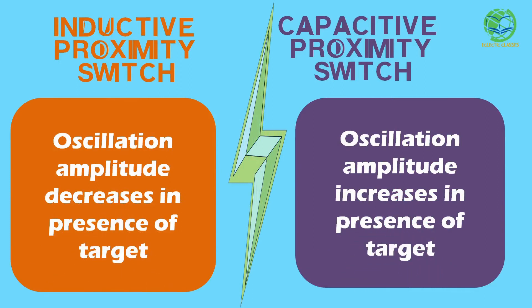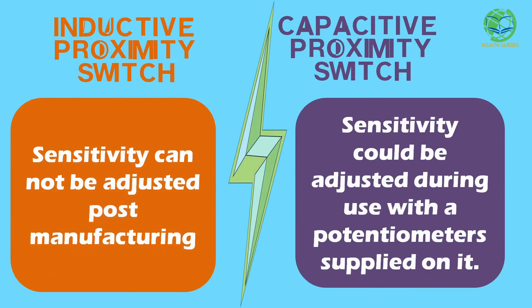In case of inductive sensors, the oscillation amplitude decreases with the presence of the target object, while in case of capacitive sensors, the oscillation amplitude increases with the presence of the target object. Inductive sensors' sensitivity cannot be adjusted, while capacitive sensors are supplied with a potentiometer to adjust the sensitivity and sensing distance.